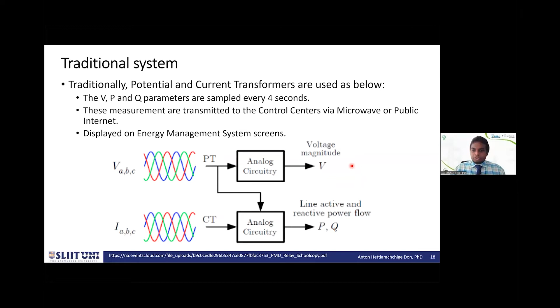The main problem is that the traditional system is not real time. If you're getting updates every 10 seconds, what you're seeing is actually what happened about 10 seconds ago. So dynamic incidents don't show up well. If the system is rapidly changing within microseconds, that won't show up on your system. So we don't have real-time situational awareness of the system.